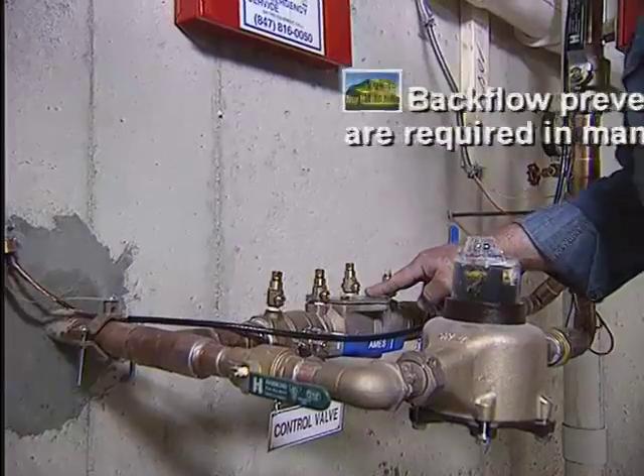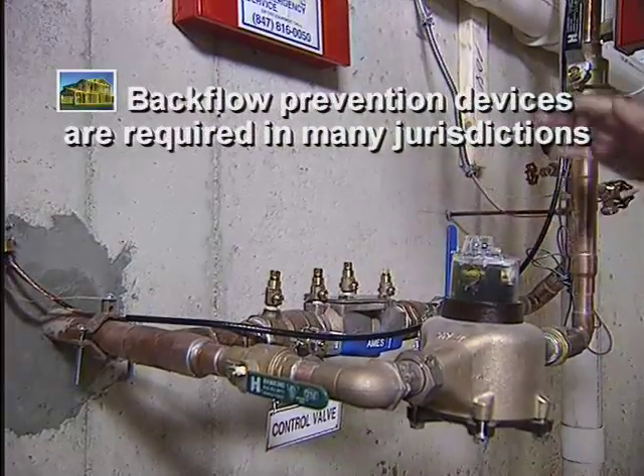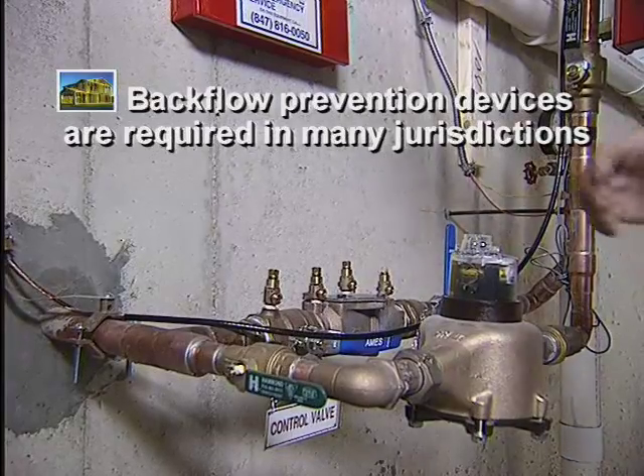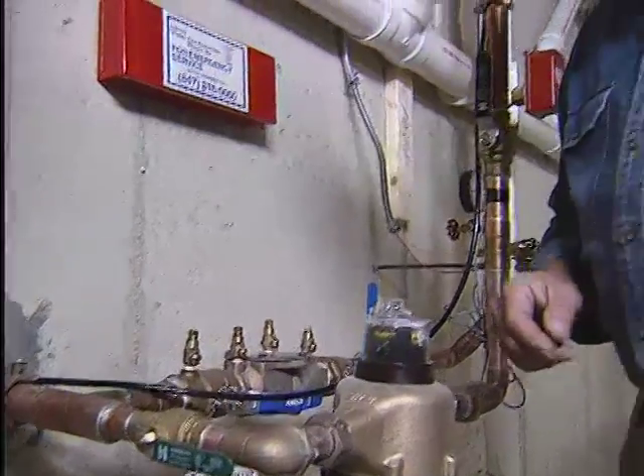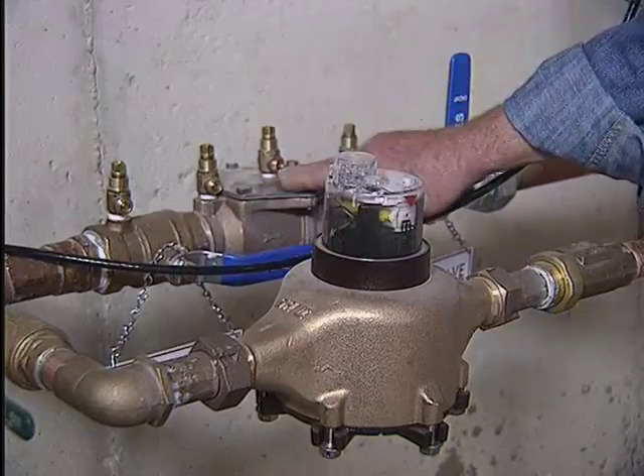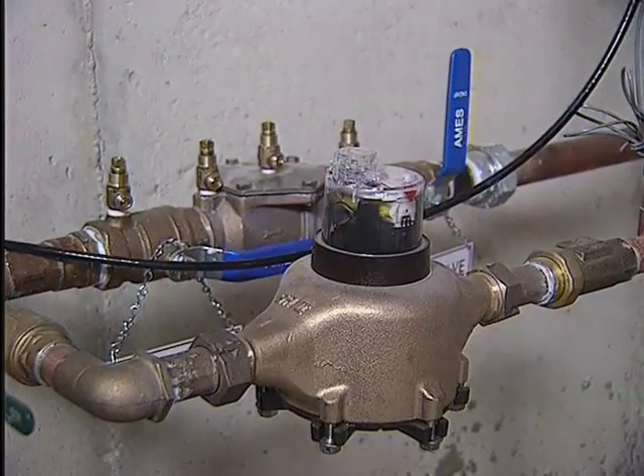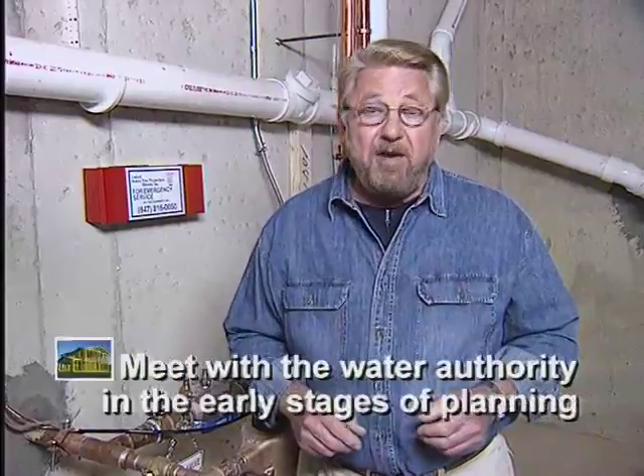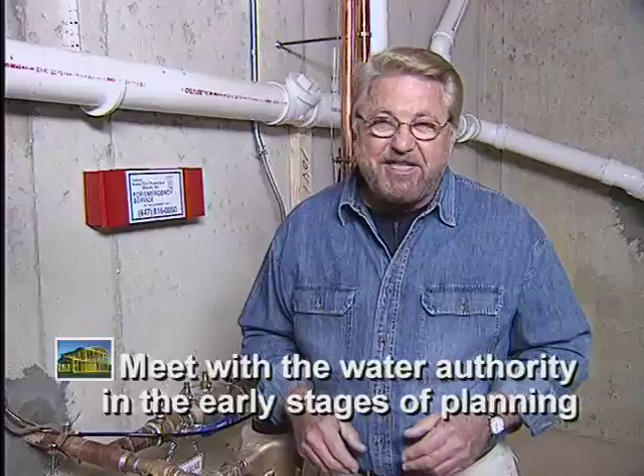While NFPA 13D does not require water flow alarms, this is one area where many local jurisdictions have additional requirements. Backflow prevention devices intended to isolate the sprinkler system from the household water supply are also required in many local jurisdictions. However, backflow prevention devices and water meters can reduce the amount of pressure available to the system. Therefore, larger taps and water meters of at least 1 inch should be installed. I strongly recommend you sit down with the Water Authority in the early stages of planning. That's the best time to discuss tap and meter sizes and any backflow issues.